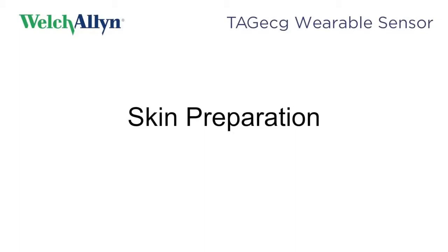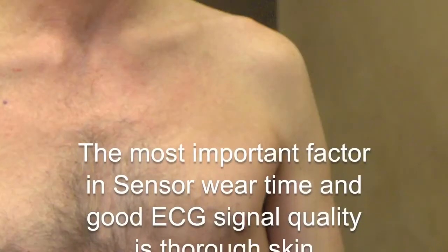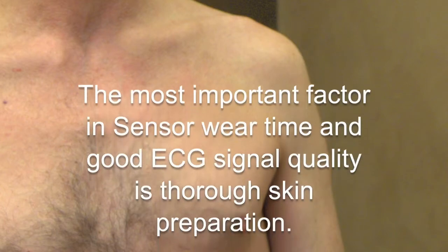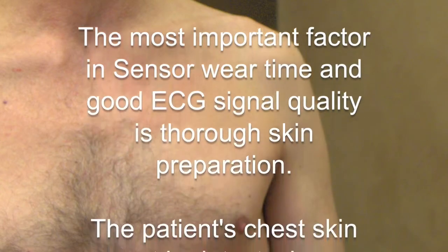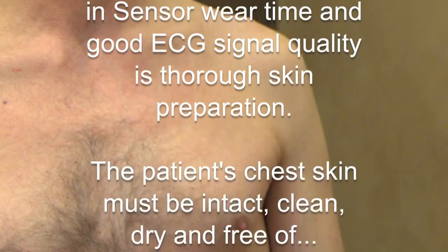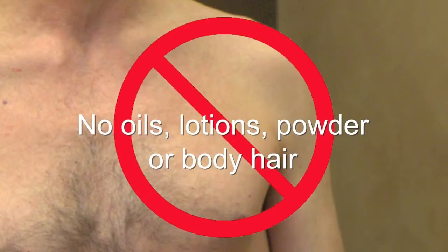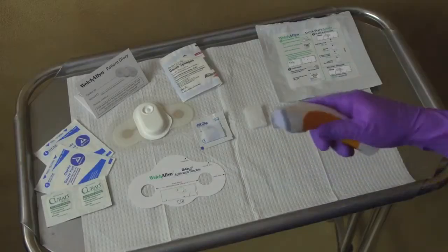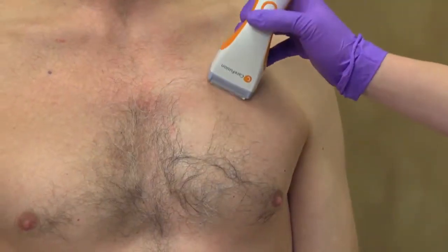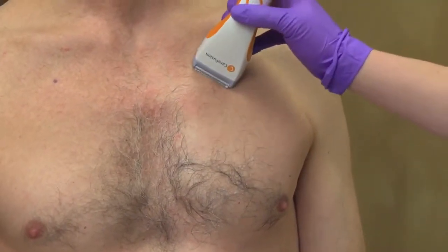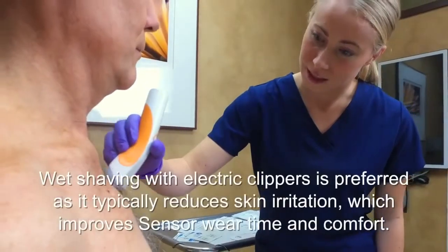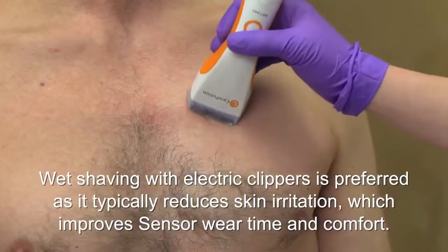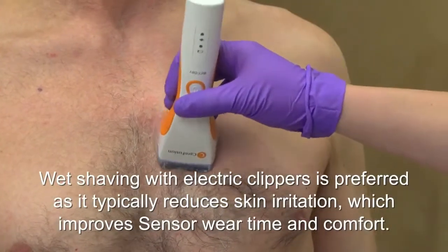Skin preparation. The most important factor in sensor wear time and good ECG signal quality is thorough skin preparation. The patient's chest skin must be intact, clean, dry, and free of any oils, lotions, or powder, or body hair before you apply the TAGecg sensor. Hair removal. Remove all chest hair growth in the area of the sensor placement on the left chest, including a full 1-inch margin beyond it. Wet shaving with electric clippers is preferred as it typically reduces skin irritation, which improves sensor wear time and comfort.